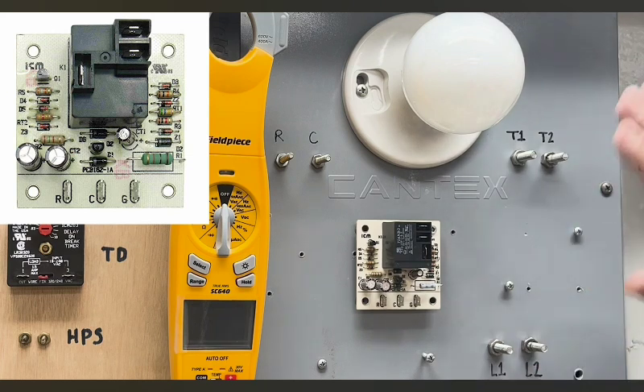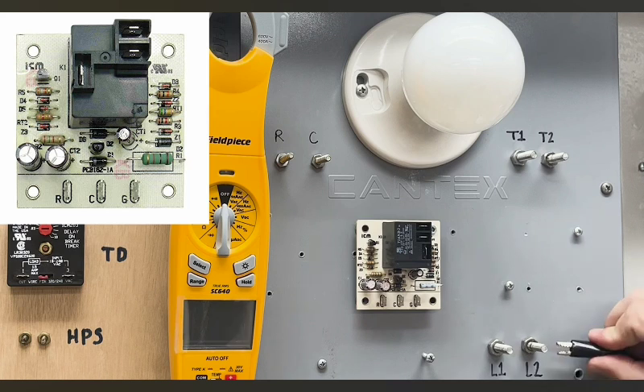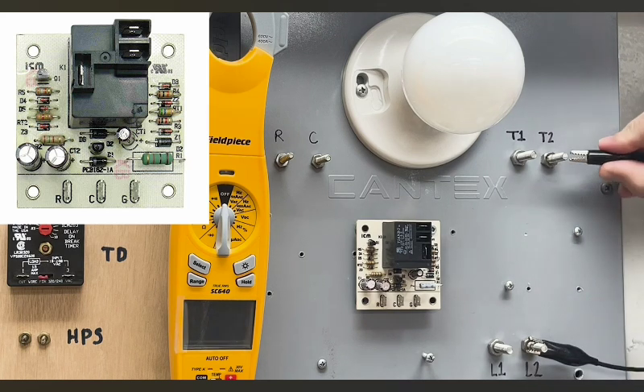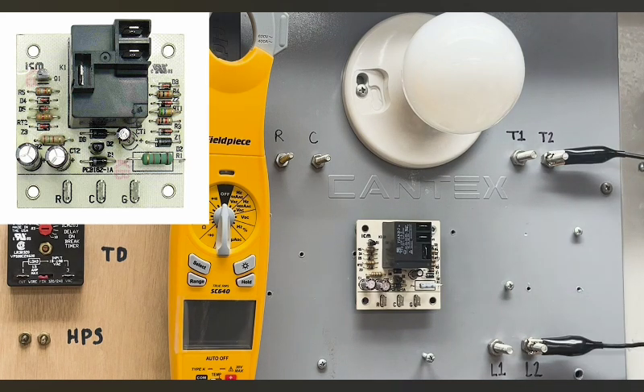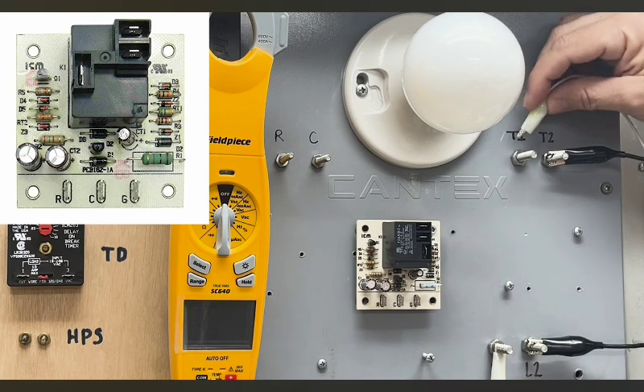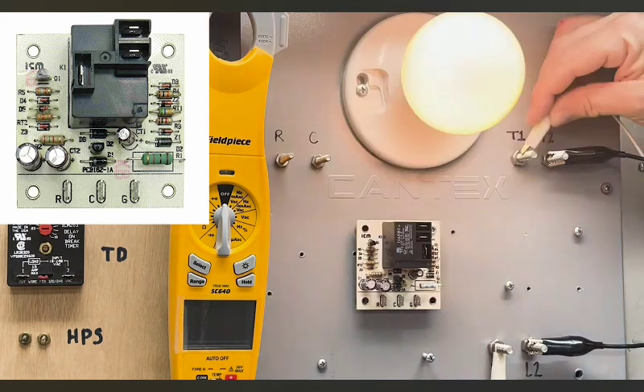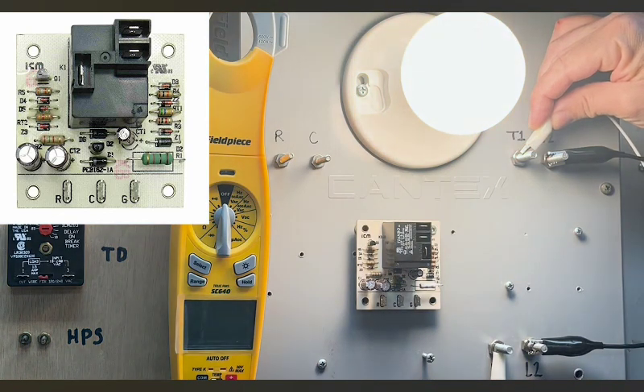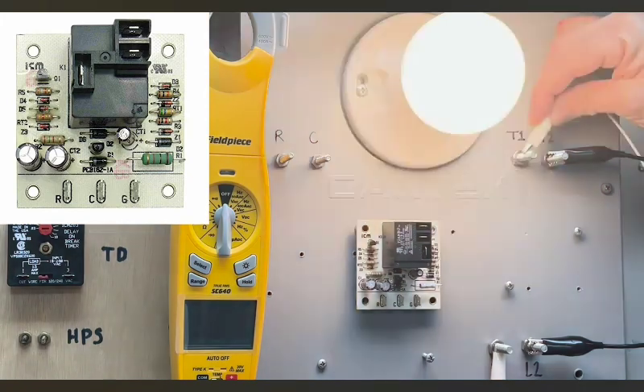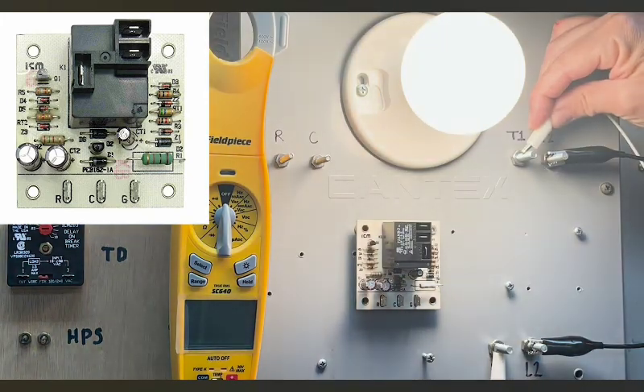I'm going to show you what happens when we just bypass the relay and go from L1 and L2 right to T1 and T2, not breaking anything. We're going to go ahead and connect L2 to T2. There's one leg of power done. We're going to go ahead and connect L1 to T1. And the moment I touch T1, the load will come on. That clicking noise that you heard is a contactor inside the box.